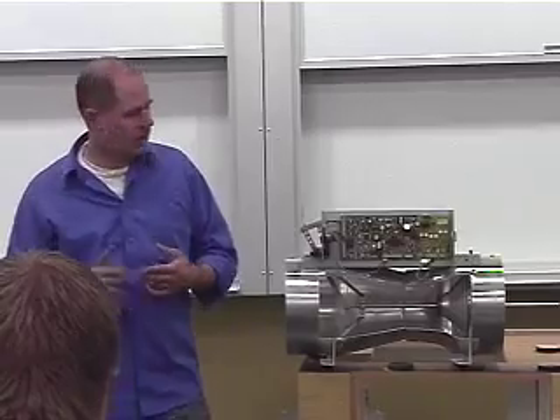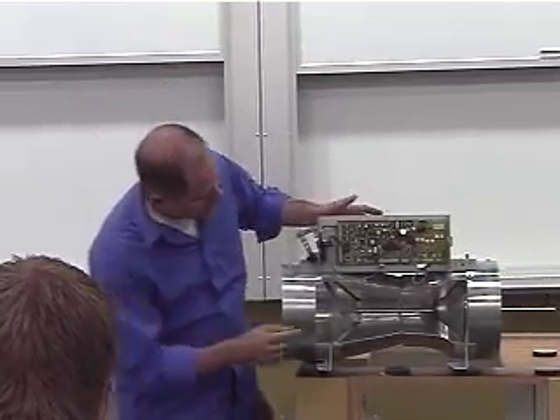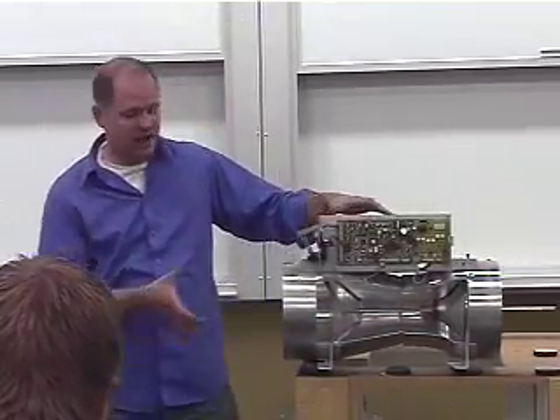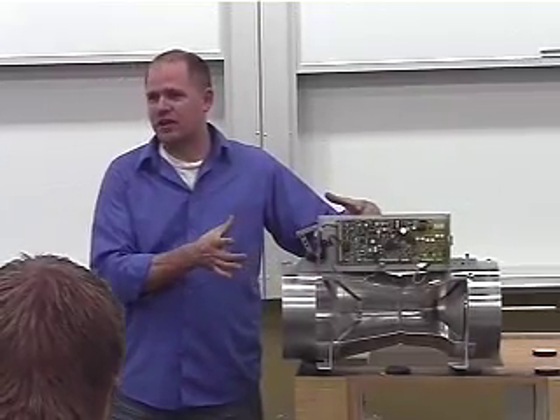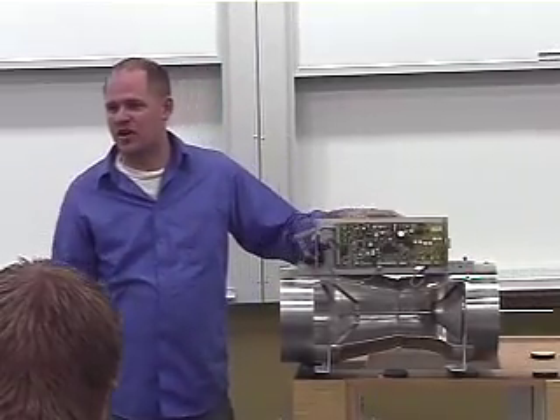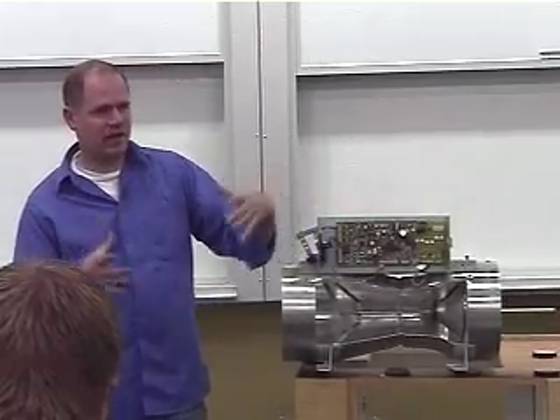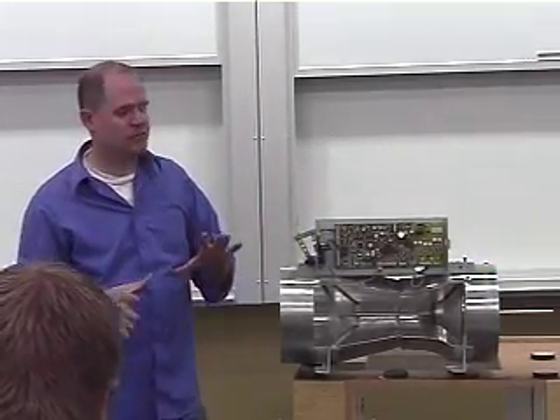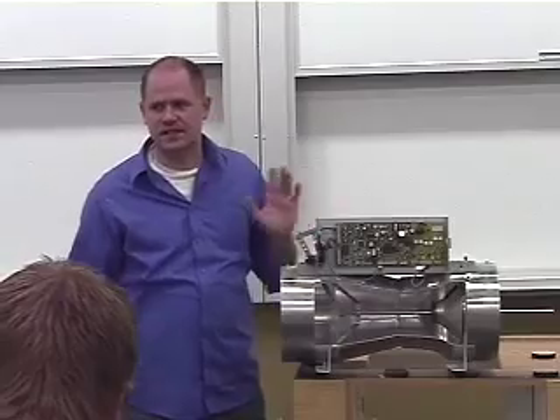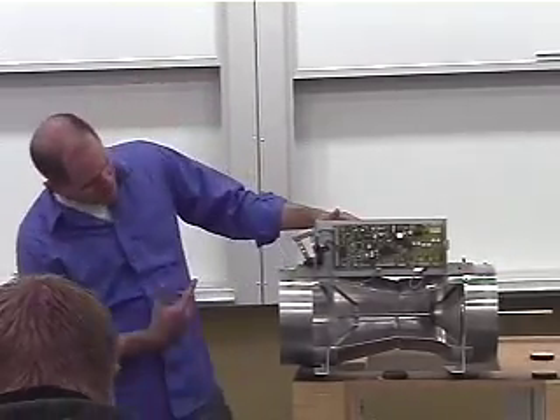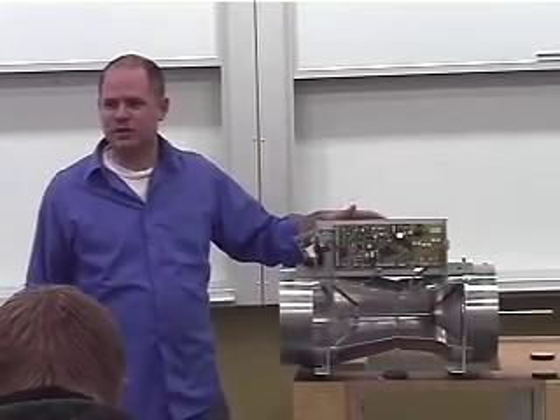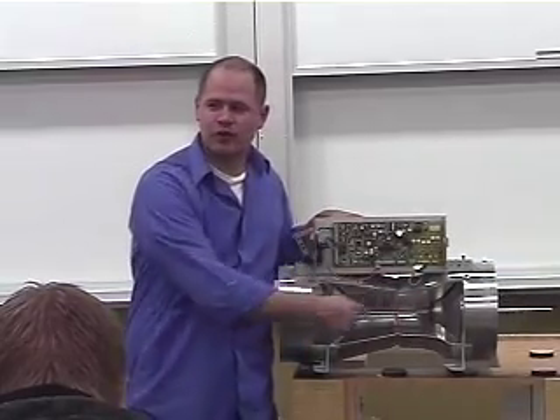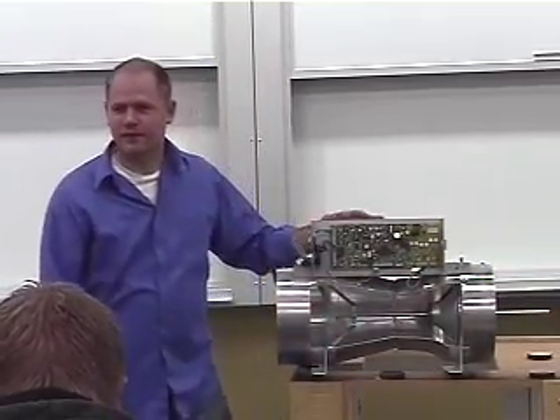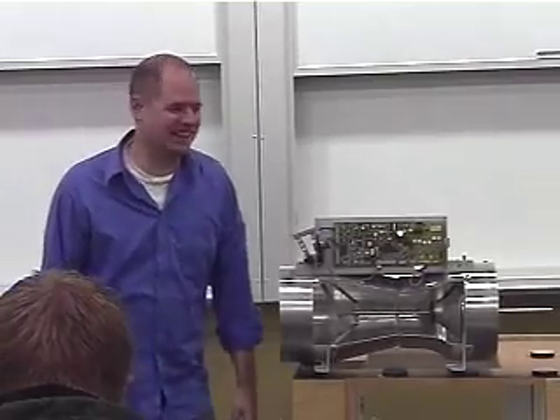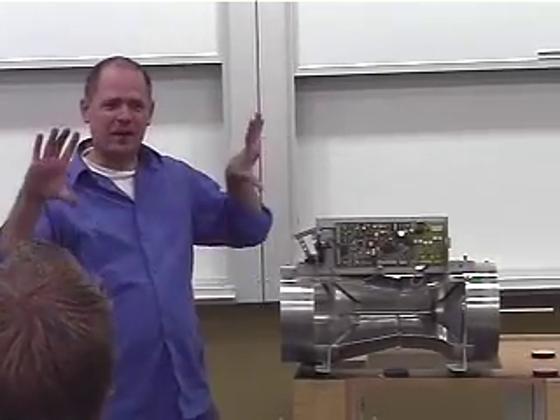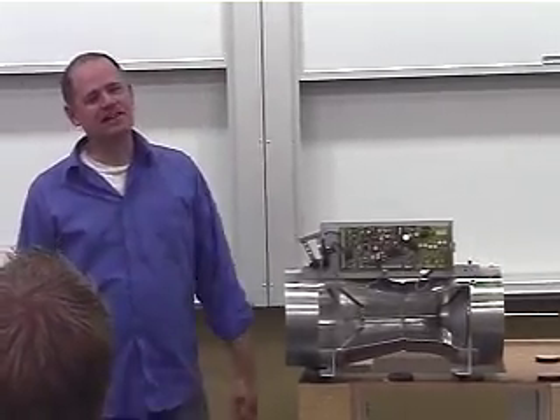How can you tell? They actually have a sticker on the cone, but if you look at the label on it, it says vertical upflow, vertical downflow, or horizontal only. It actually says it on a big label with the arrow and everything on production valves. This one's obviously a test demo one, which you can swap out the cone at any time and change which one it is. And they have a big hole. Yours don't have holes in them like this. I know. It'd be really nice to have a nice big window on every one of them so you can look in there and say, oh, look inside.